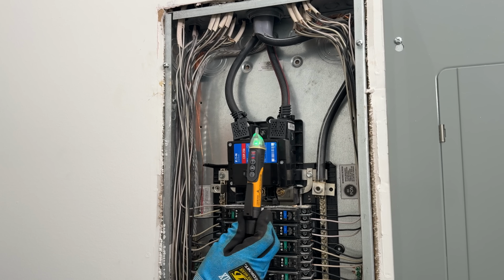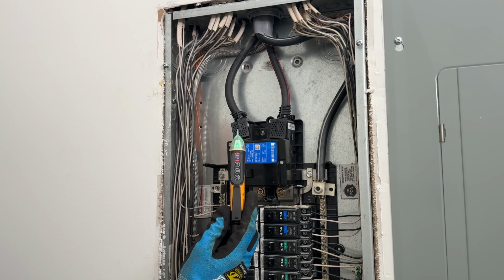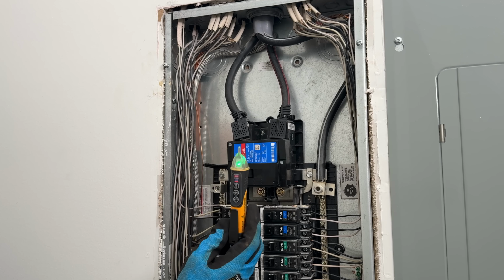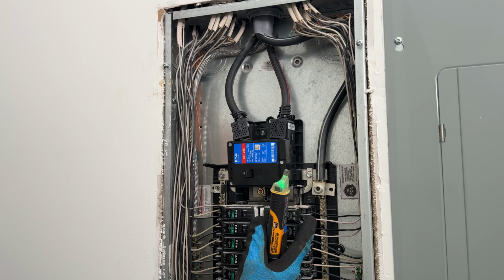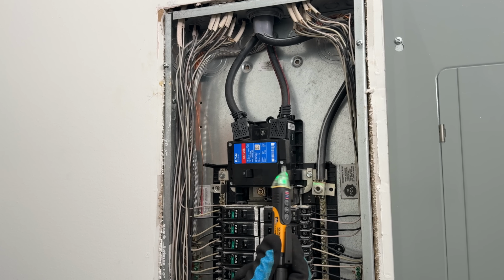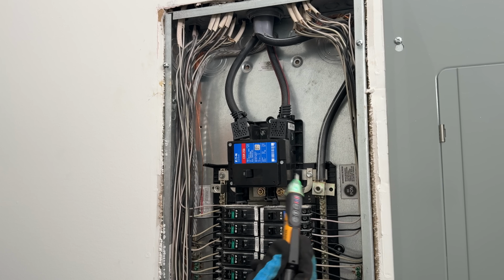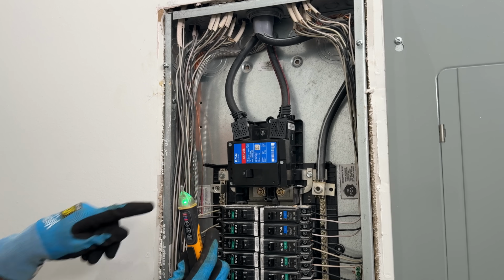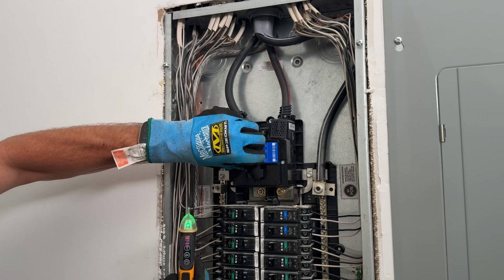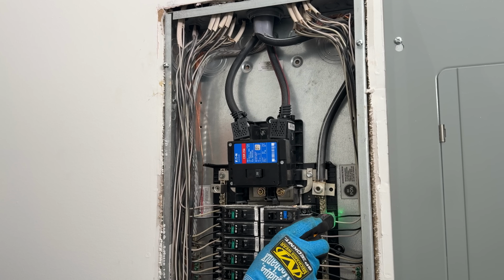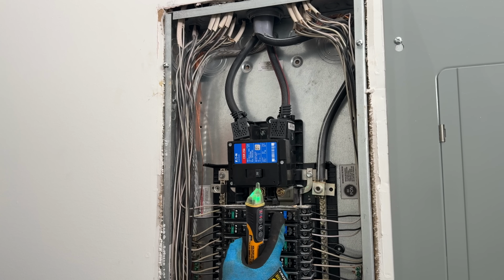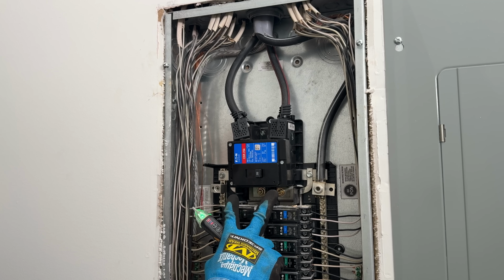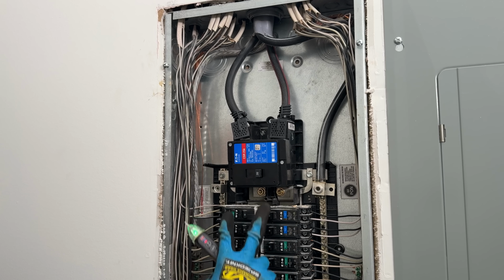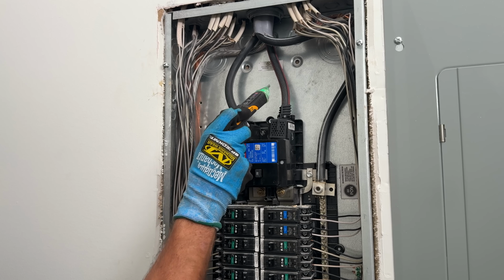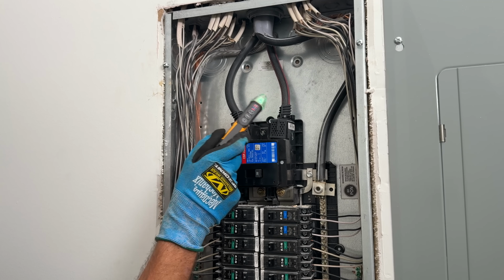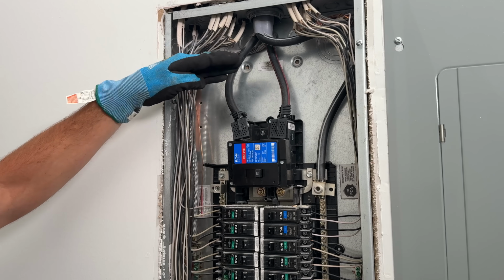Now, before I do that, I'm going to test my non-contact voltage tester just to confirm it's working properly. With these breakers on, I would expect my black hot wires would read out hot, as they are. In addition, even when I turn this off, and now confirm that I'm no longer getting power at the hots coming from the circuit breaker, because now we have turned off power to the 2 bus bars, we still have power at our main hot conductors coming in on the top side here of our panel.